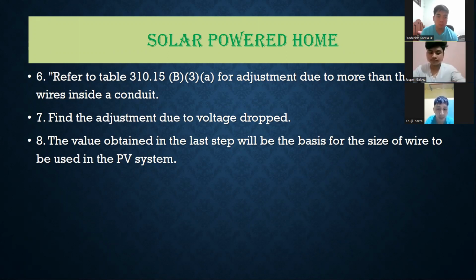So in step 6, we have an adjustment if we have more than 3 wires in a conduit. Now for step 7, we find the adjustment due to the voltage drop. We'll be having a formula for that later. And then step 8, the value obtained in the last step will be the basis for the size of wire to be used in the PV system. So now let's have an example.